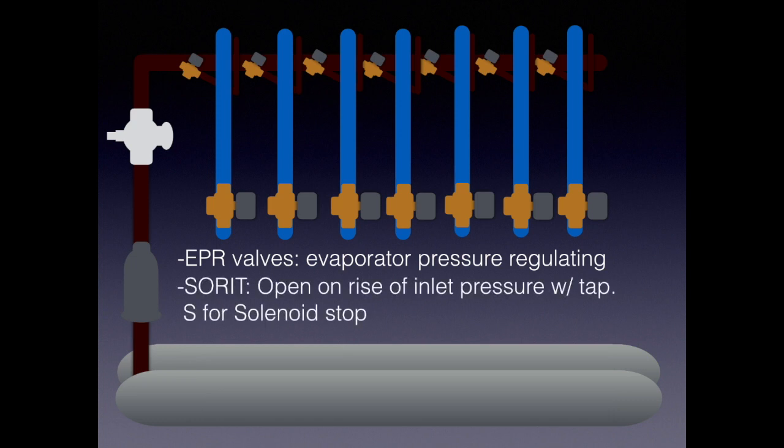These valves that control the EPRs are SORIT. In this case they have the solenoids. So SORIT is a solenoid controlled valve that opens on rise of inlet pressure and has a Schrader tap. So you have your SORIT and your ORIT and really the only difference is the solenoid stuff.